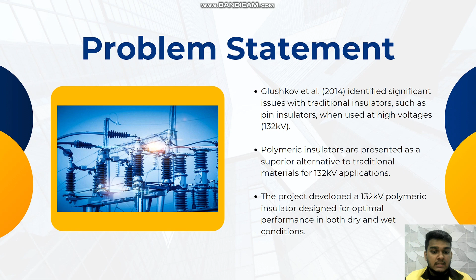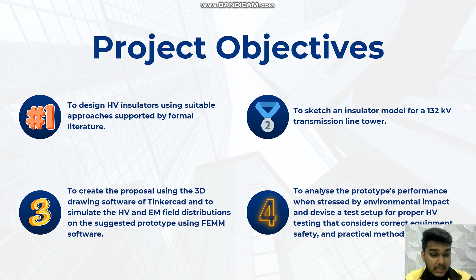Next, let's see the project objectives. Firstly, to design HV insulators using suitable approaches supported by formal literature, and to sketch an insulator model for a 132 kV transmission line tower. Then, to create the proposal using the 3D drawing software Tinkercad, and to simulate the high voltage and EM field distributions on the suggested prototype using FEMM software. Lastly, to analyze the prototype's performance when stressed by environmental impact and devise a test setup for proper HV testing that considers correct equipment, safety, and practical method.